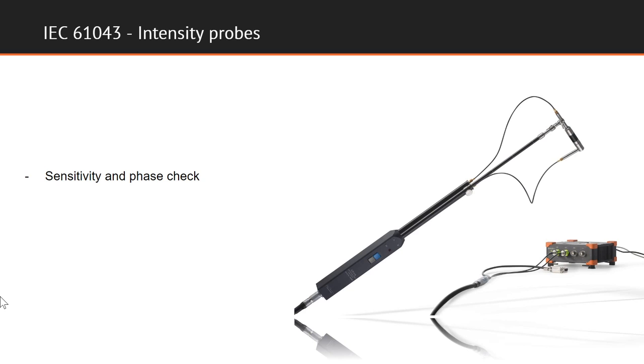Sound intensity probe calibration procedure consists of sensitivity and phase check. The sensitivity of the microphone pair is measured by comparison with a reference microphone, according to the same procedure as described in IEC 61094 for calibration of measurement microphones. In addition to sensitivity measurement and phase check, the pressure residual intensity index for the complete system is also calibrated in accordance with the demand stated in IEC 61043.